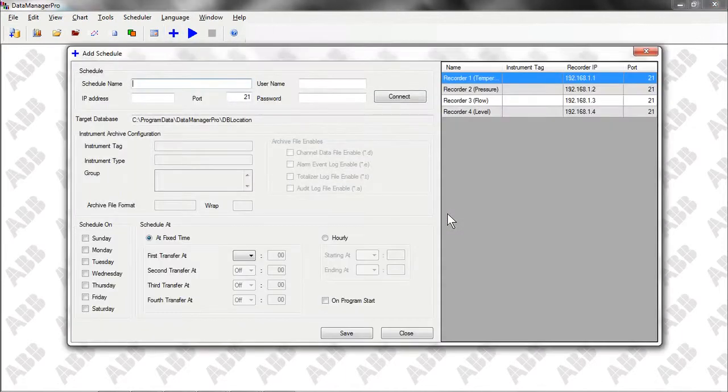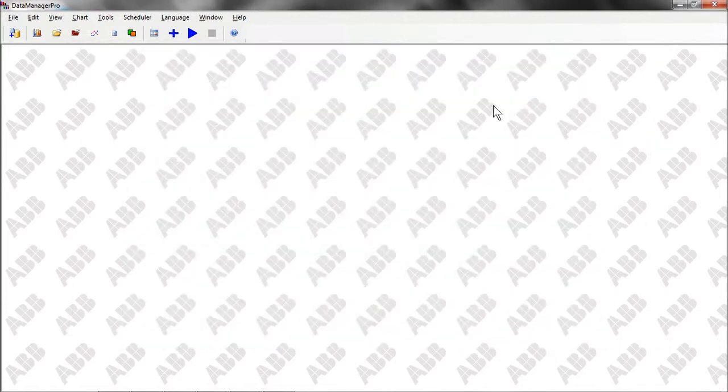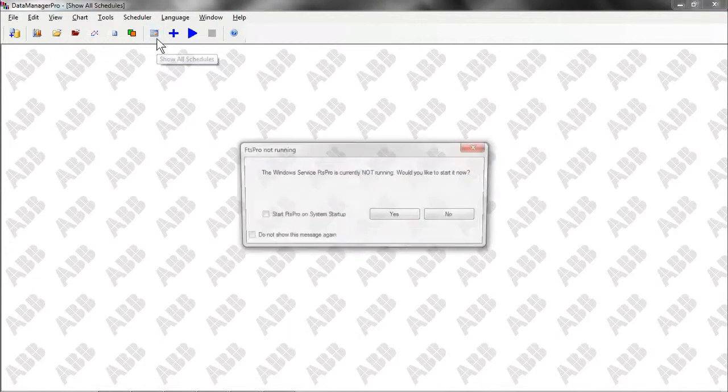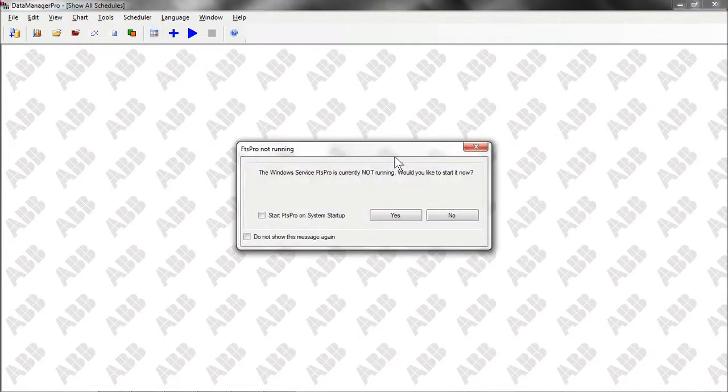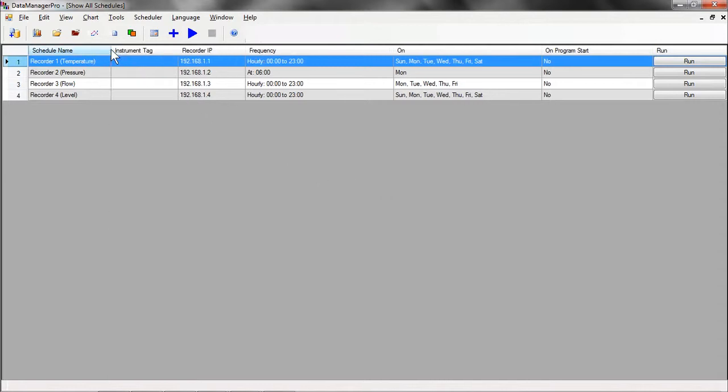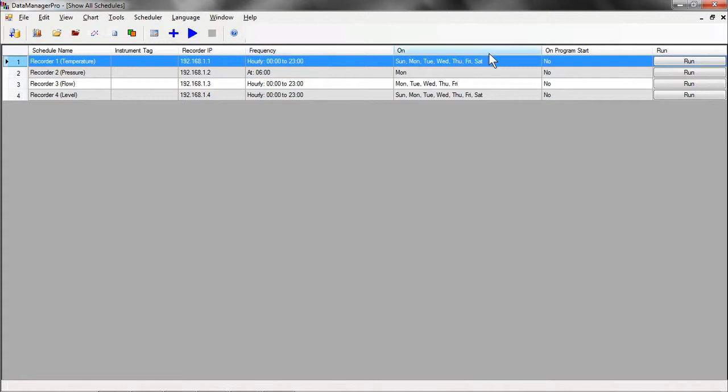This window is used to set up the automatic collection schedule. Clicking on this icon will display a list of all the schedules we have already set up. Here, we can see the names of the recorders Data Manager Pro is going to collect data from, and how often it's going to collect it. In this case, the frequency has been set as every hour of every day. When data is collected, it's also automatically imported into the database so that anybody viewing a chart will see the most up-to-date information.